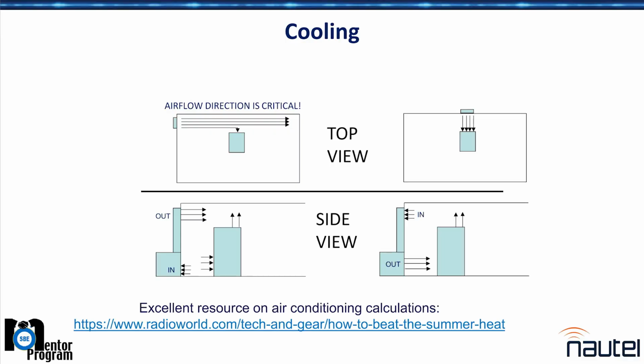So if we can send the cooling air out low where the air intake is, and put the warm air return up high at ceiling height, which is where every transmitter I'm aware of, except the low power ones, dumps the heat, it will save a whole lot of air conditioner cycles. It improves the efficiency. It's going to make it a little less comfortable for the transmitter tech standing in front of it, but a whole lot more effective for cooling the equipment.